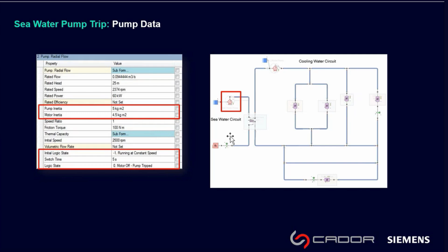It's very easy to set in the component itself. Once you have set the data, you can run the model in Flomaster in transient form, and then you can simulate the rotational speed of the pump. The pump will quickly, over a few seconds, based on its inertia, come to rest, and as a result, you will start to see the temperature rise in different heat exchanger components. Because when you start to lose capacity, in this case we only have one pump, so if you lose the pump which is supplying the coolant or fresh water cooling in the circuit, then obviously it's just a matter of time before we start to see temperature exceeding the range that we set, perhaps 115 or 120. So you can then estimate how long it will take for a total failure. In this case, it's showing us it will take just over 4 minutes to have a complete failure.